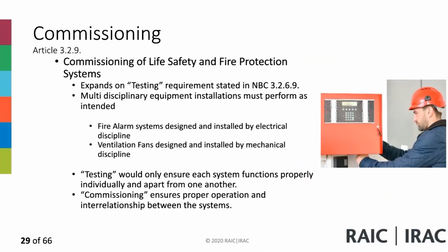Commissioning, 3.2.9. We talked about it briefly under module 1. 3.2.9 is a critical new addition to the building codes, and it's not actually commissioning. It's called integrated fire protection and life safety system testing. It used to be referenced as commissioning, but it's not. The OBC references it as commissioning. The NBCC actually in 3.2.9, if you go to that subsection, it's called Integrated Fire Protection and Life Safety Systems Testing.